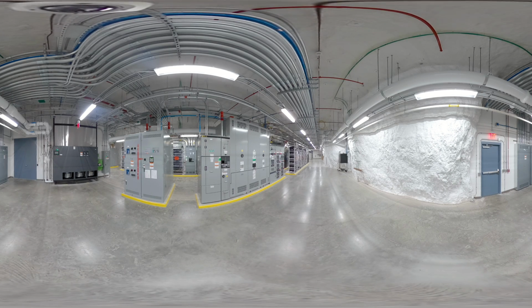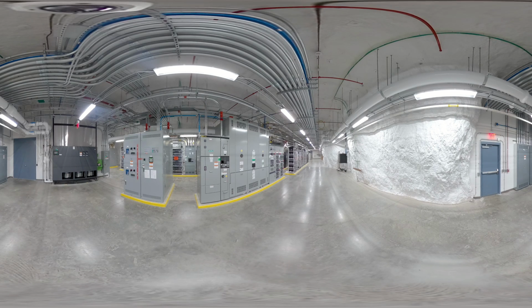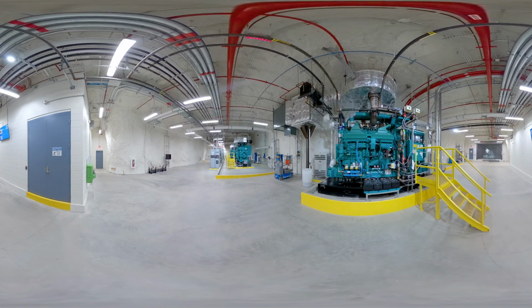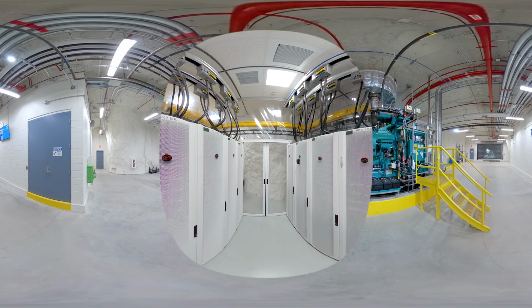3 separate utility substations in a grid design provide 2 diverse utility feeds to the data center's fully redundant service entrances. Our generator system has a present capacity of 21.5 megawatts to support a block redundant configuration. Generators can run at full load for 72 hours before needing refueling.